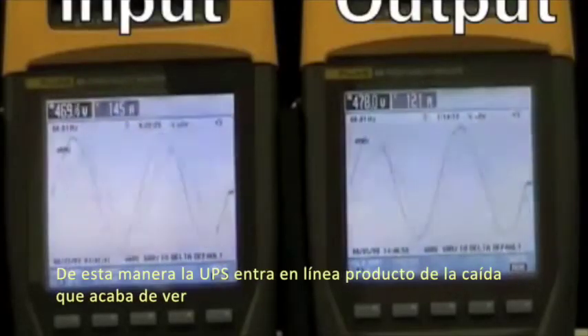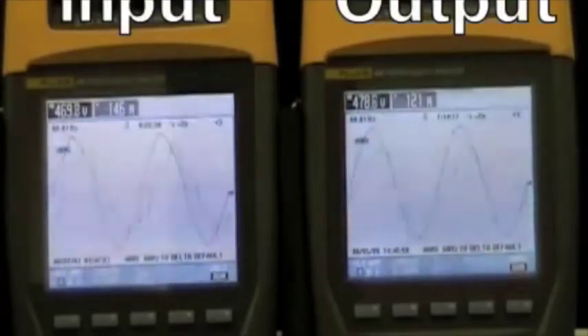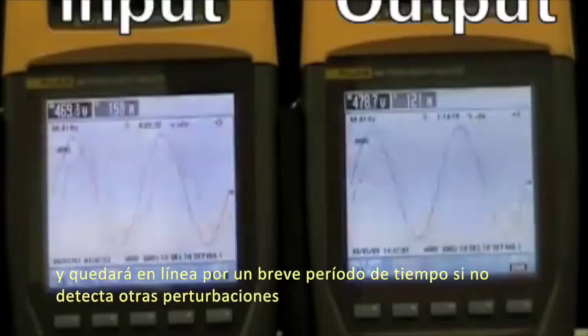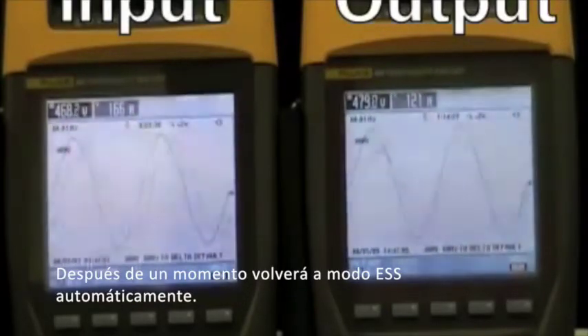So the UPS comes online as a result of the sag that we just saw. It will remain online for a short period of time, and if no other disturbances are detected, after a moment it will go back to ESS mode automatically.